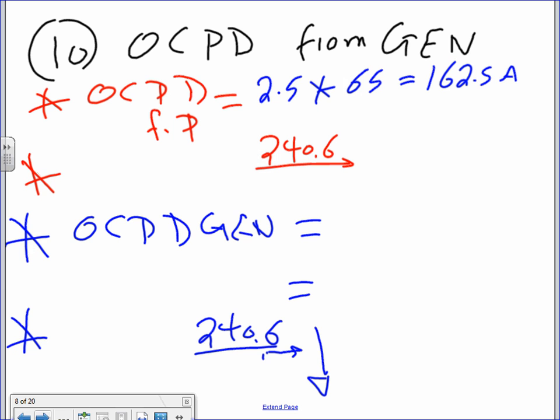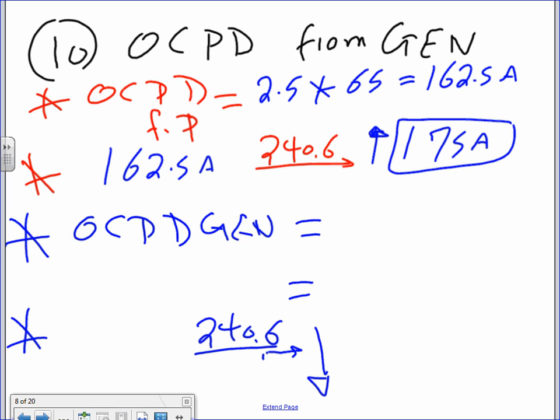Then you take the 162.5 amps, take it to 240.6, go up if it's not a standard, and that will give you a healthy 175 amp circuit breaker. Okay? We're not done yet. Listen, we're not done yet. So that's what you're going to get.